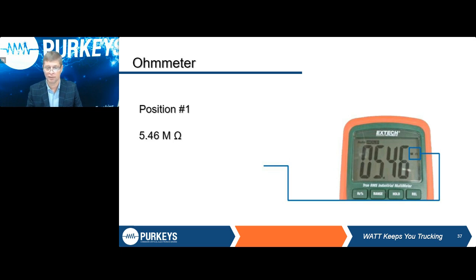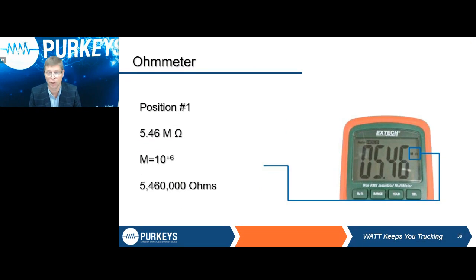The answer is the sensor's good. All the manufacturer was asking for was a resistance value of at least 6,000 ohms to be considered an open or an infinite reading. Your meter doesn't say 5.46 ohms. If you see that big M there, that meter is actually telling you 10 to the 6th power. So that is 5,460,000 ohms. That's a bunch of them.